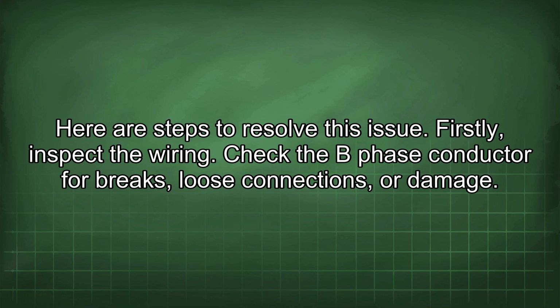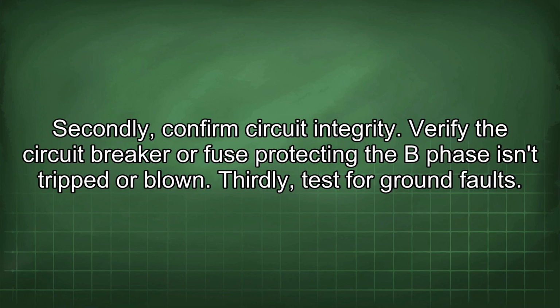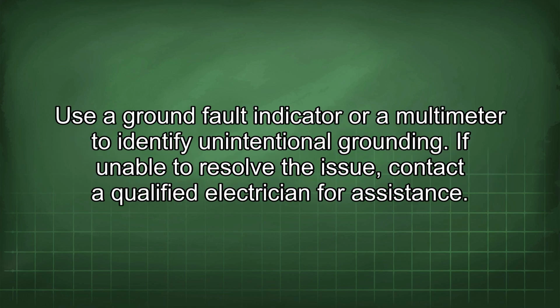Firstly, inspect the wiring. Check the B phase conductor for breaks, loose connections, or damage. Secondly, confirm circuit integrity. Verify the circuit breaker or fuse protecting the B phase isn't tripped or blown. Thirdly, test for ground faults. Use a ground fault indicator or a multimeter to identify unintentional grounding. If unable to resolve the issue, contact a qualified electrician for assistance.